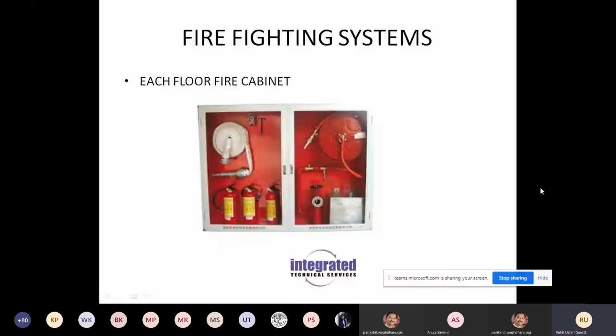Now, this is the fire cabinet that I was talking about on every floor. If you see, this is the landing valve on the right, where you can connect this hose over here. You can connect it to this landing valve, but this is to be operated only by firefighting personnel who are trained to handle this pressure and discharge. Then you can see the first aid hose reel and the tapping for the first aid hose reel through a small pressure reducing device, so that a much lower flow is available and at a much more manageable pressure.